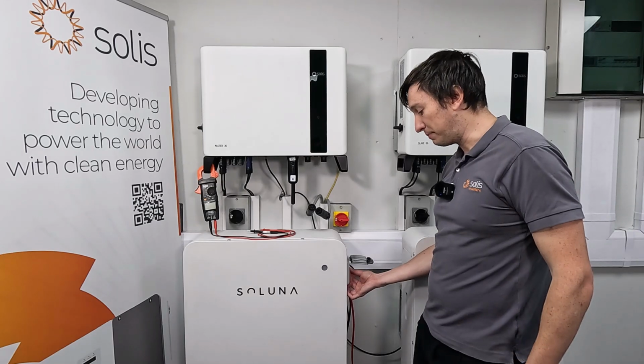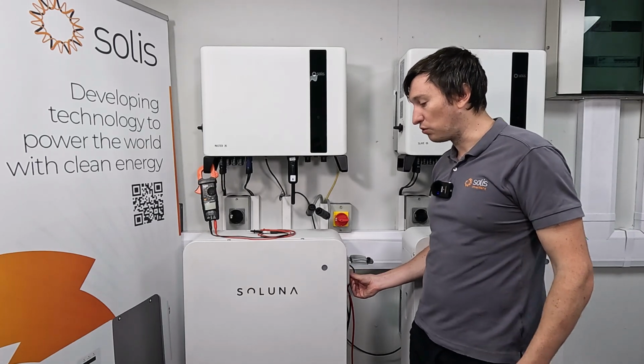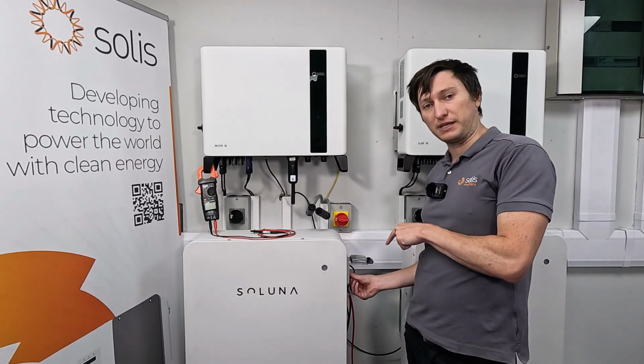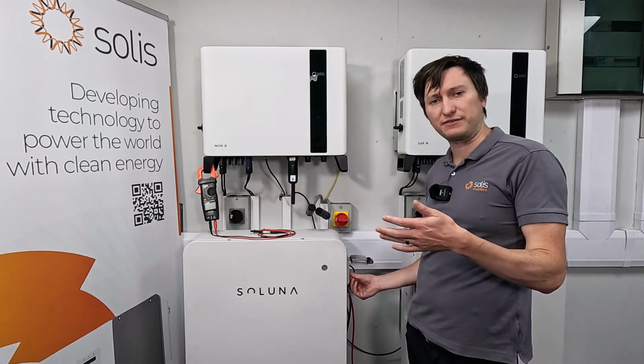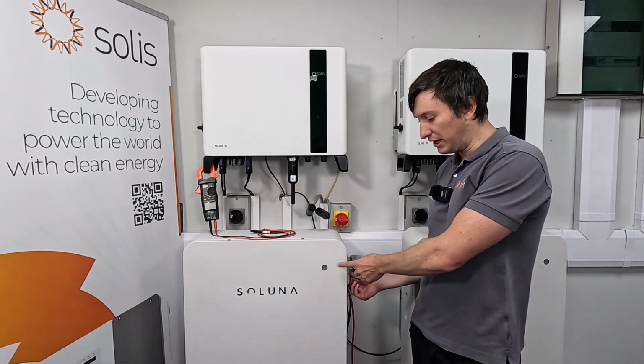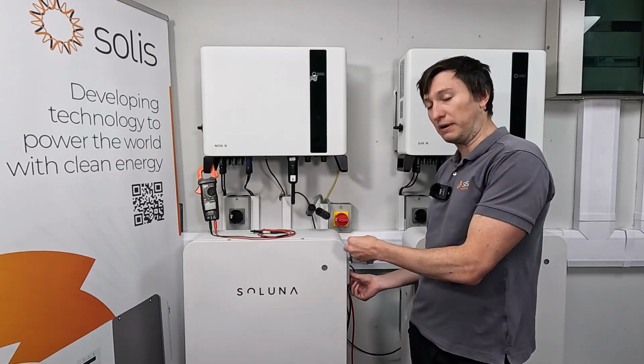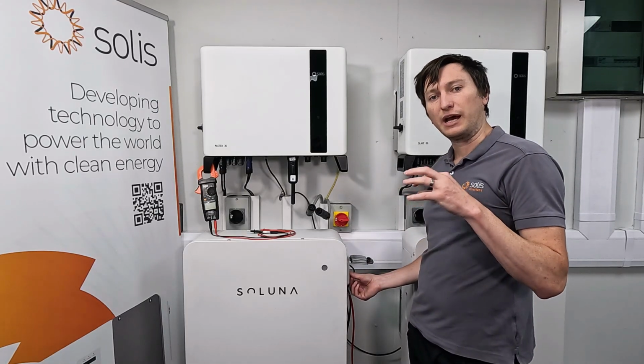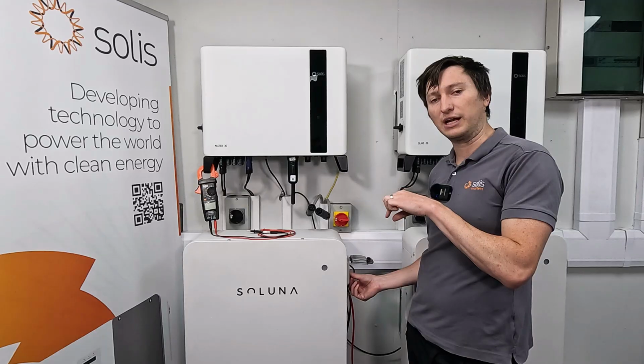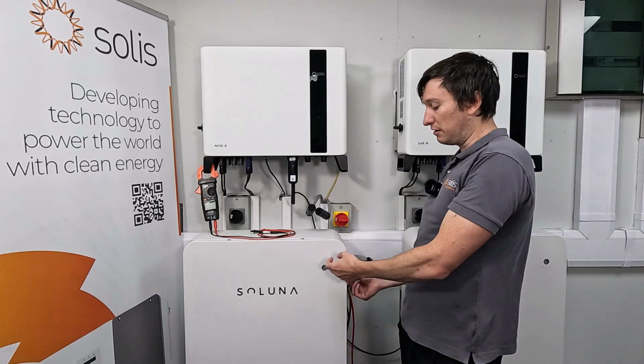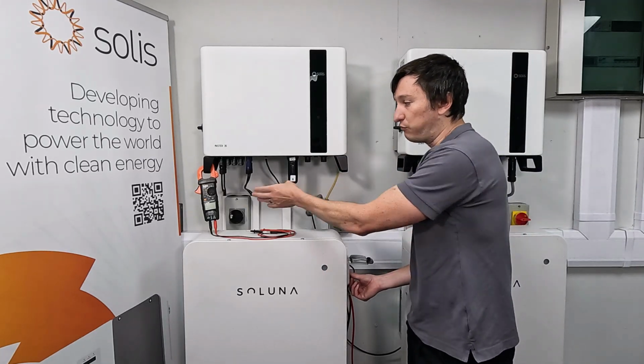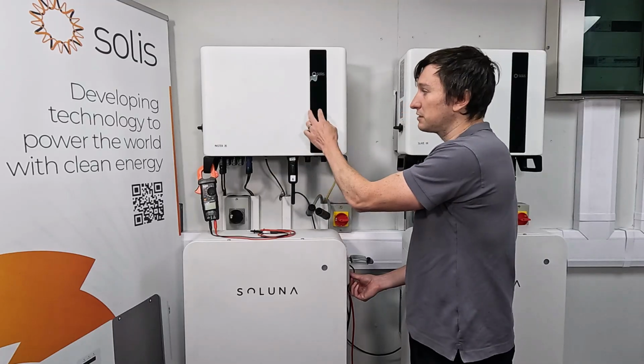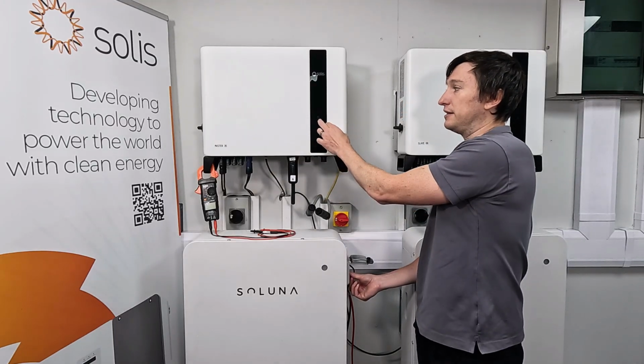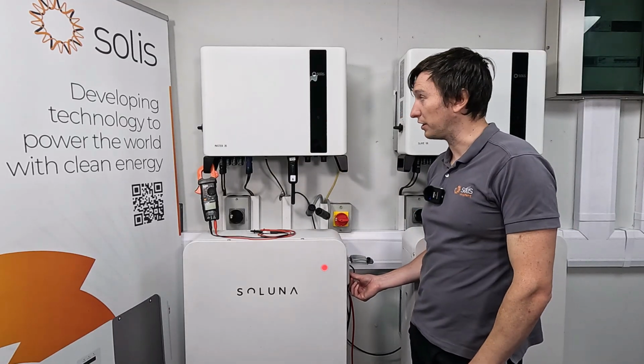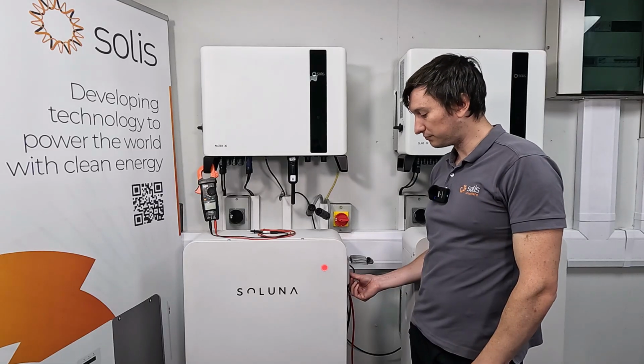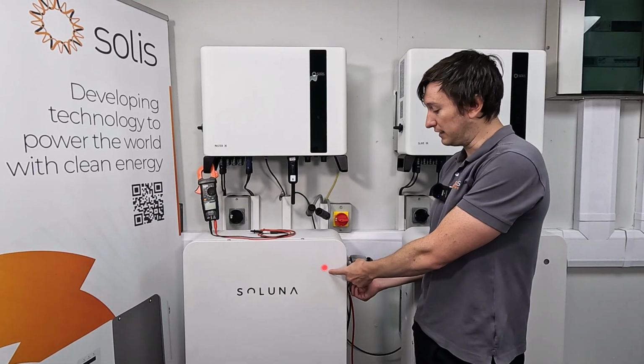I'm going to turn on the battery isolator and press and hold the start button on the battery for about 25 seconds, I think, for this battery. This LED here will go blinking red as a caution, then solid red, and it'll click the relays closed, and you should see solid red here. If we measured the voltage across those pins, we'd see voltage, and the inverter should also be turning on at that stage. So there we've got a solid LED here.